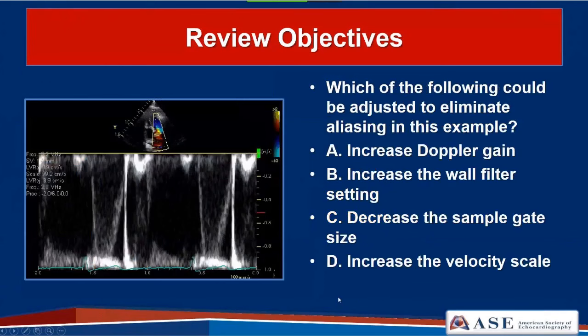Next review question: which of the following could be adjusted to eliminate aliasing? Increased Doppler gain will just make the spectrum look more noisy but won't eliminate aliasing. Increasing the wall filter setting—we don't have significant baseline clutter here. Decreasing the sample gate size—the gate is already small; making it larger would cause spectral broadening. Increasing the velocity scale is the correct answer: by increasing the velocity scale, we are increasing our pulse repetition frequency, which eliminates aliasing.